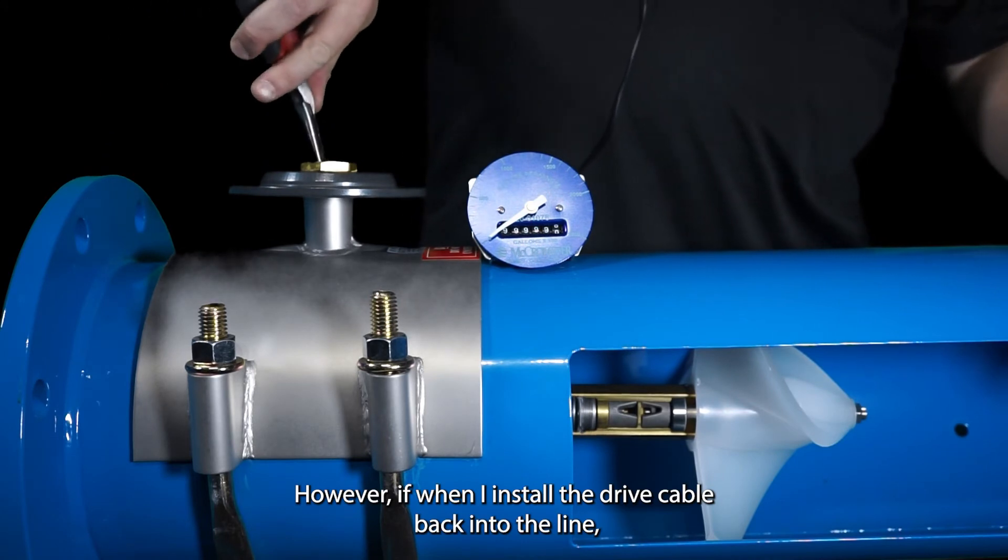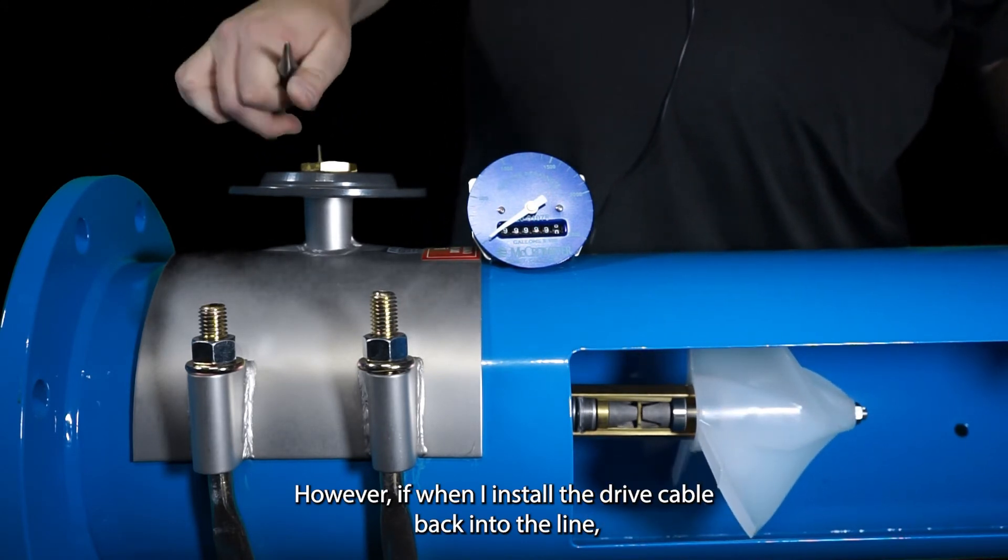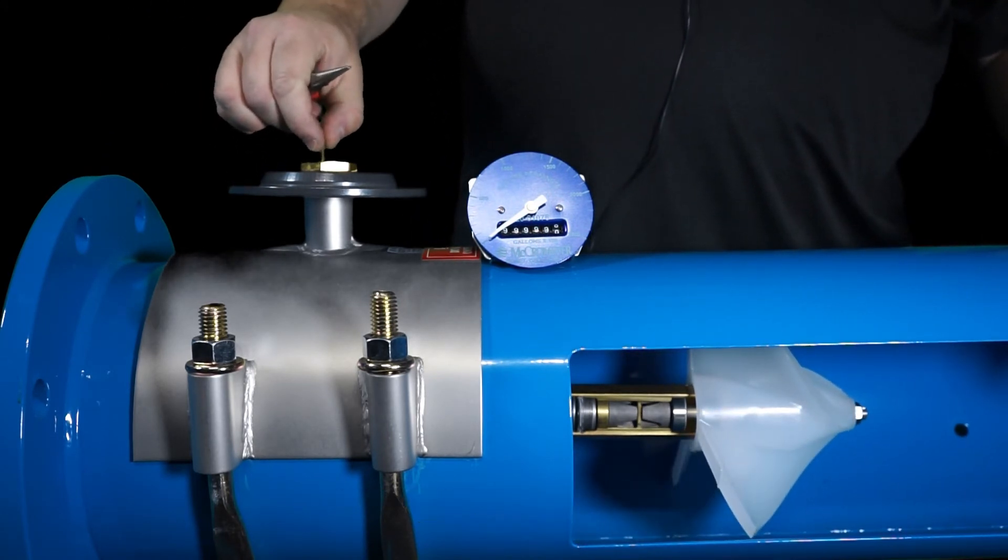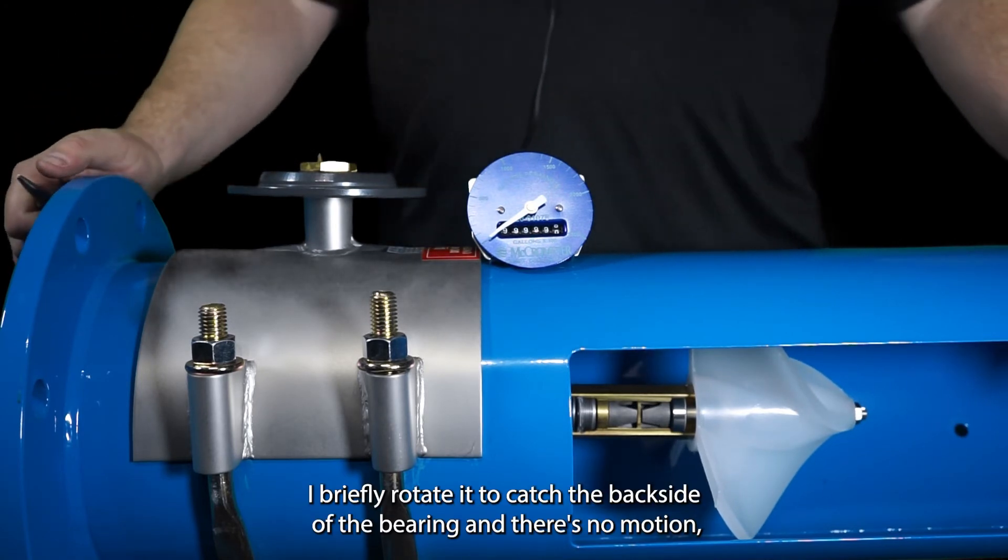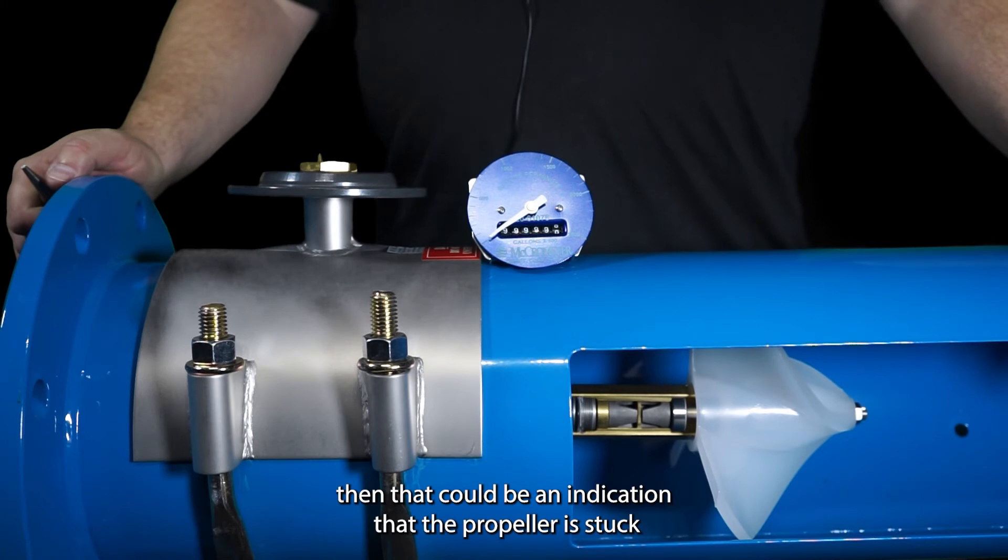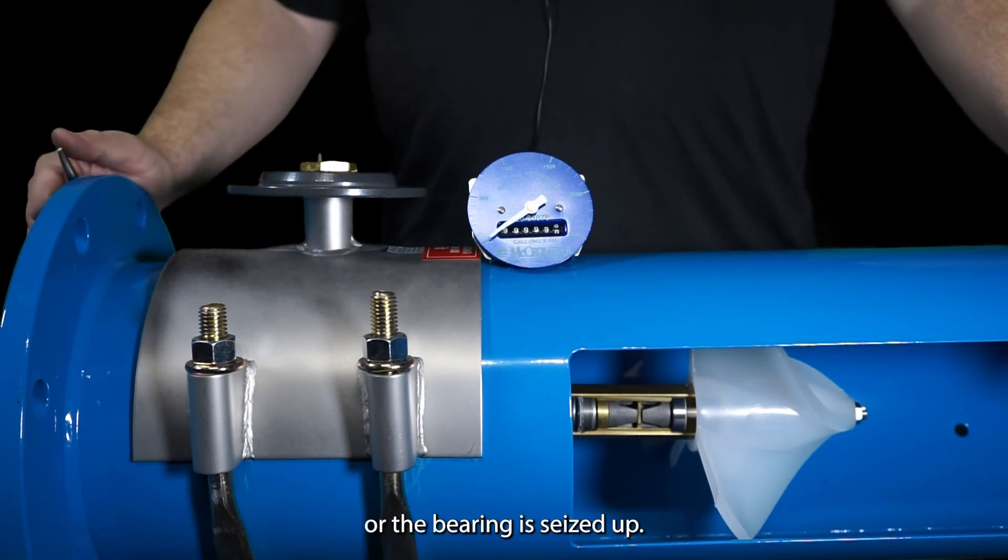However if when I install the drive cable back into the line I briefly rotate it to catch the back side of the bearing and there's no motion then that could be an indication that the propeller is stuck or the bearing is seized up.